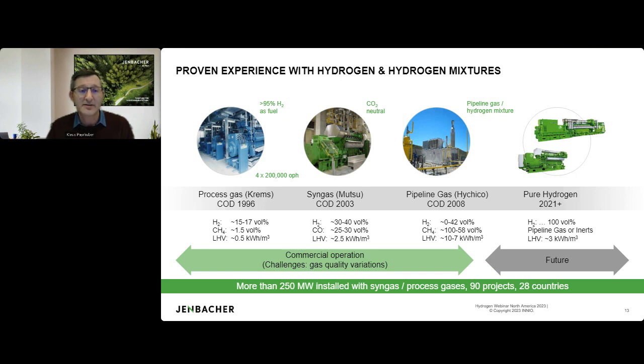On the left-hand side, you see an example from Austria, where we installed 4 engines about 25 years ago, containing 15 to 17 volume% hydrogen. But when we look at the fuel, about 95% of what's in this fuel is hydrogen and burns as hydrogen—the rest is typically nitrogen. All these engines have achieved 200,000 operating hours, so we have really long-term experience burning hydrogen.